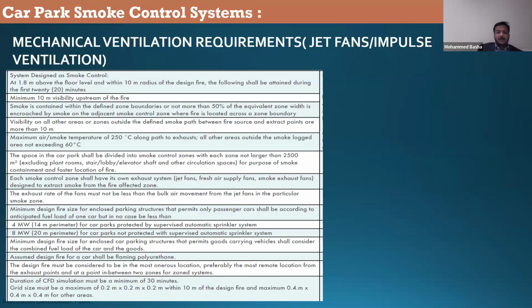So your volumetric flow rate required for 4 megawatts will be different from that for 8 megawatts. This is based on the sprinkler activation time. This is why they mentioned the sprinkler activation time. I told you, if you don't know the fire Q value, you have to simulate different conditions. Simulate for 2 megawatts, 3 megawatts, 4 megawatts, and see at what time the sprinkler activates and what your tenability conditions are at that time. So they have made their study and given us 4 megawatts and 8 megawatts as a reference. It's a very good reference, basically.